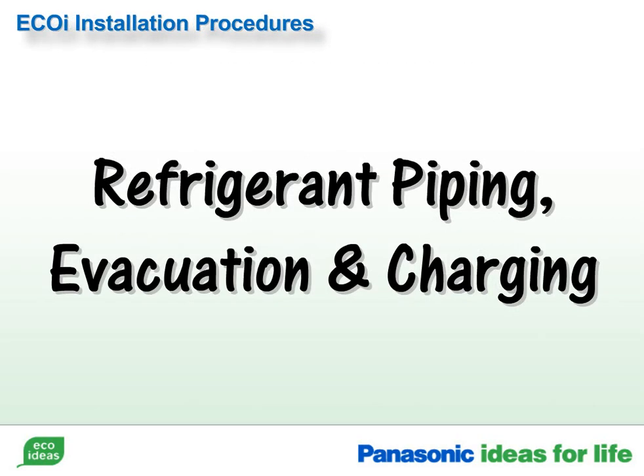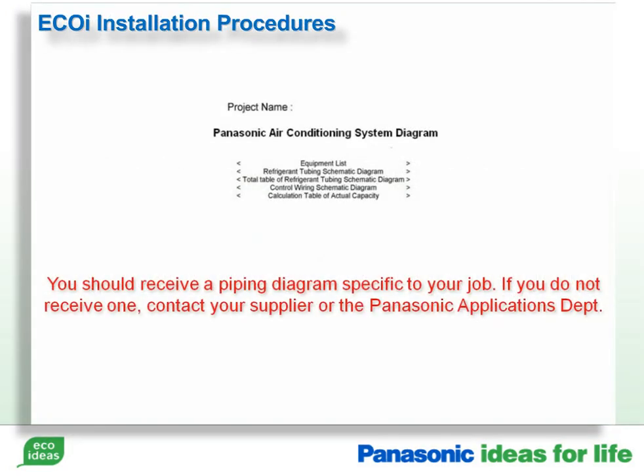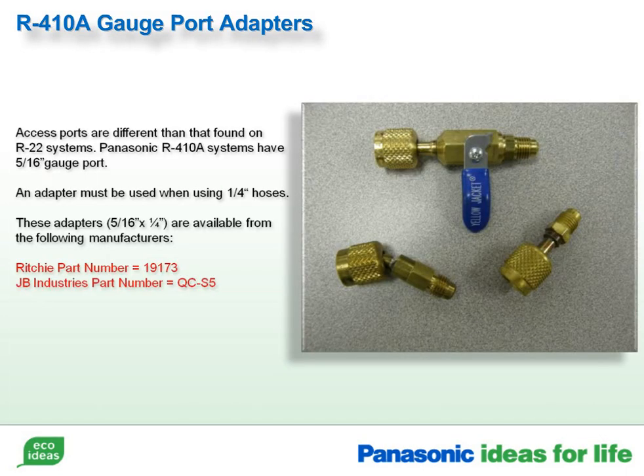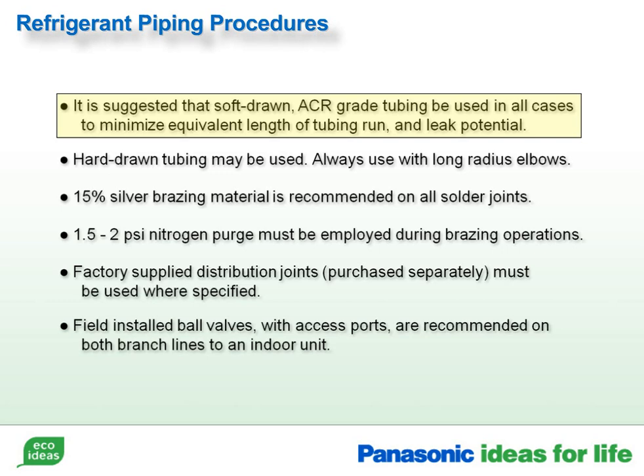Refrigerant piping, evacuation and charging procedure. The Panasonic designed software is used to create piping and wiring diagrams for each job. These drawings will be provided by your Panasonic representative. All Panasonic 410A condensers use 5/16 gauge port connections. You will need one of these adapters in order to connect gauges to any Panasonic unit. It is suggested that soft-drawn, ACR-grade tubing be used in all installations. This will minimize equivalent length of tubing run and leak potential.